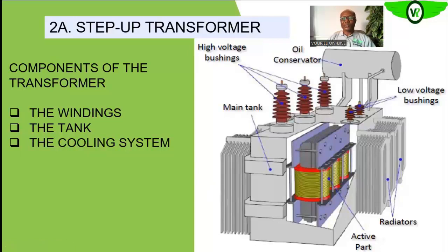Okay, so we know that once the transformer is loaded, heat energy will be released. That is because of the I squared R losses. So that power that is lost when the transformer is working, we need to remove from the transformer, or else it may degenerate to a situation where it will just fail. The insulation of the winding will completely fail. So since we need to remove this heat, we need a system that will help us to do exactly that, and that is what the cooling system does.